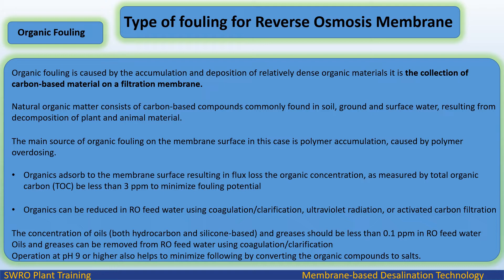Organics adsorb to the membrane surface resulting in flux loss. The organic concentration, as measured by total organic carbon (TOC), should be less than 3 ppm to minimize fouling potential. Organics can be reduced in RO feed water using coagulation/clarification, ultraviolet radiation, or activated carbon filtration. The concentration of oils, both hydrocarbon and silicone-based, and greases should be less than 0.1 ppm in RO feed water. Oils and greases can be removed from RO feed water using coagulation.